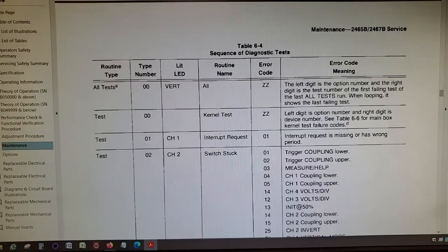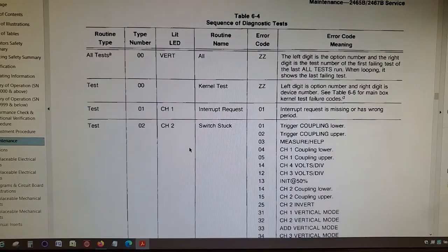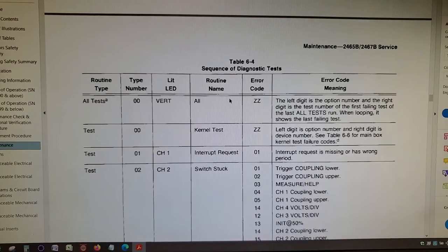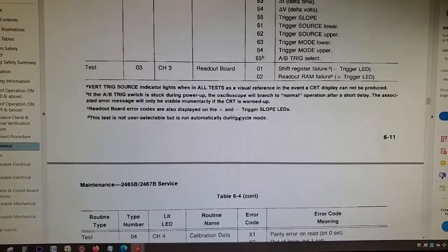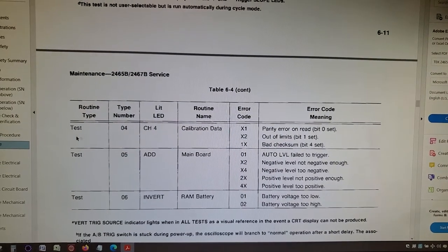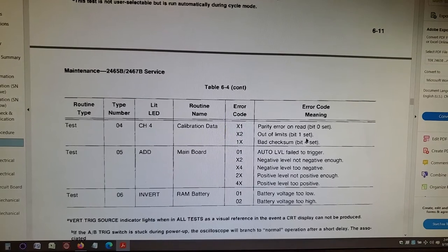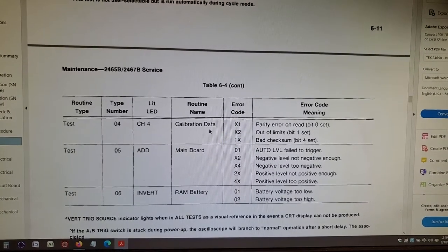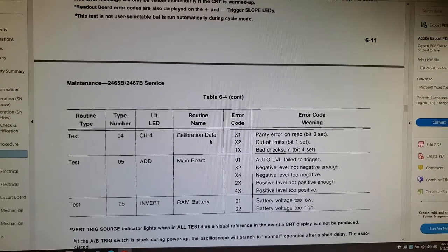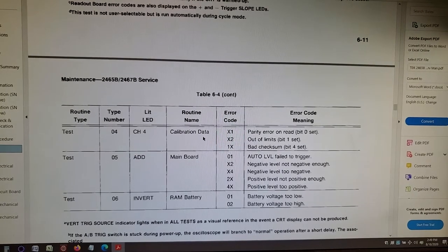Okay, I just went over to the screen here to look at test four. Scroll down - and this is in table 6-4 by the way, on table 6 or page 6-11. So you go down here to where it says test 4-0-2: out of limits, bit one set, meaning that the calibration data is incorrect. It means the scope needs to be calibrated or there was a fault during calibration, which that scope has. Doesn't mean the scope is not usable, it just means it's not accurate.